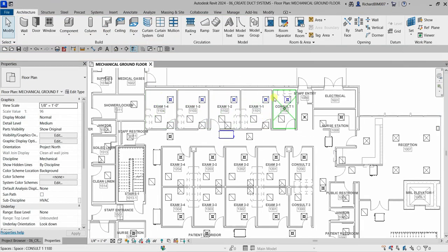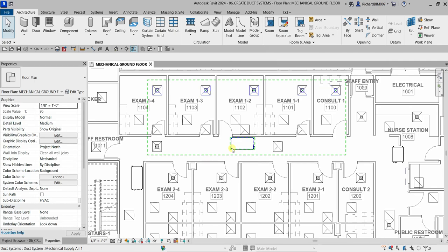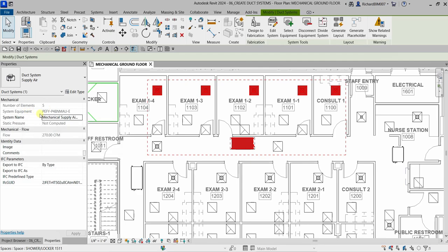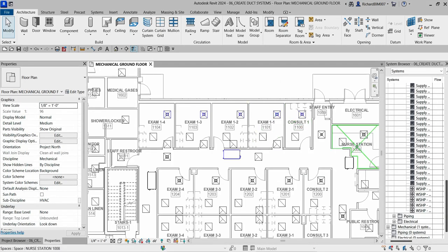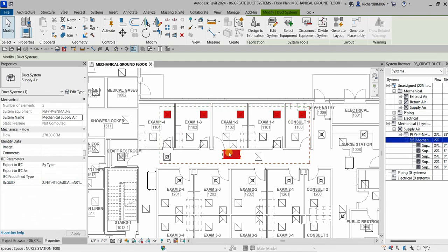The color of the system elements turns blue once the system is created. If you hover your pointer over the mechanical equipment — don't click, just hover — and press Tab once, it will highlight the system on that equipment. Click to see the system name and flow based on the air terminals. In the System Browser, you'll now see one system listed. Expand it to see the system and its assigned elements highlighted.